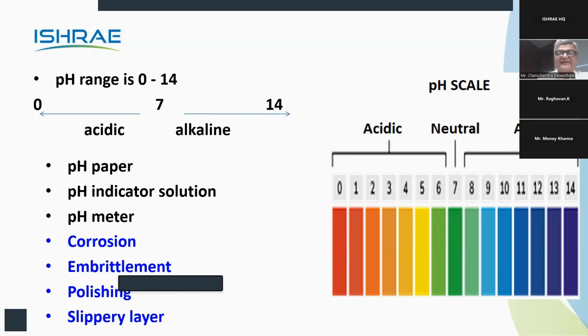See, 0 to 7 is the acidic range. As you go from 7 towards 0, the acidic intensity goes up - a pH close to 0, which is normally not there, would be highly acidic compared to 7. And when you go from 7 to 14, 14 is highly alkaline compared to 7. So alkalinity goes up from 7 to 14, and acidity goes up from 7 to 0. Acidity is directly connected with corrosion, and alkalinity is directly connected with deposition, fouling, etc.